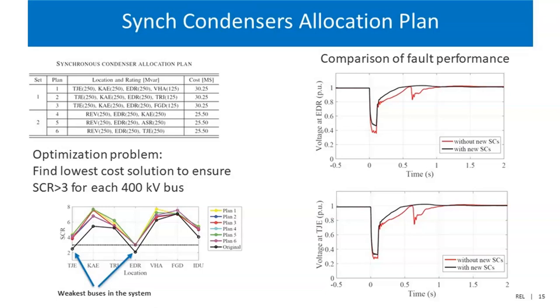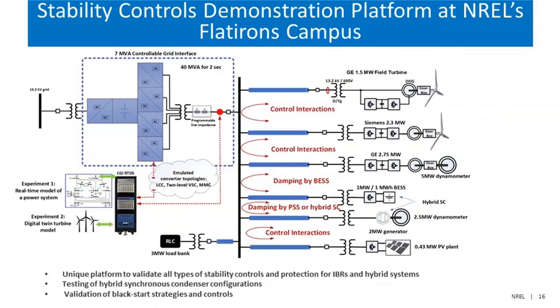So in order to address this type of issue and many other issues that we talked about, going back to NREL capabilities, this is a more detailed view of the validation platform we developed that consists of grid simulators and also real multi-megawatt utility scale renewable generation and existing energy storage. And as I said, we're adding a 2-megawatt generator to one of our dynamometers to make it operate as a synchronous condenser as well.